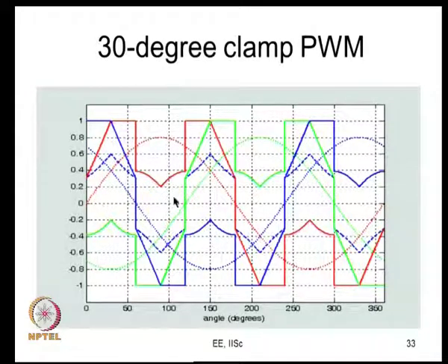What will happen here is you will find that the highest current carrying phase will not get clamped, but the second highest current carrying phase will get clamped, which is the best thing that you can do in this case.